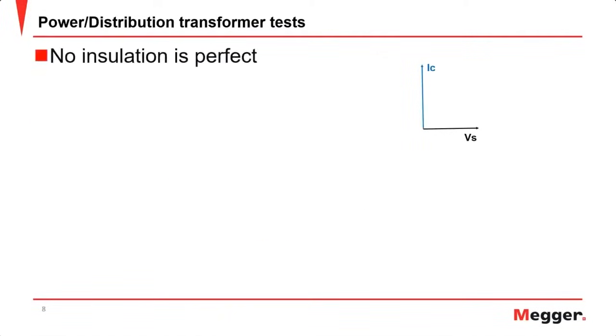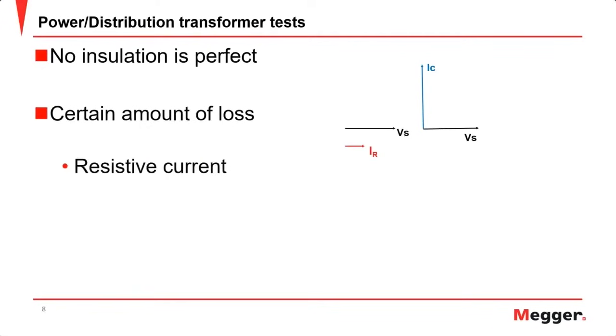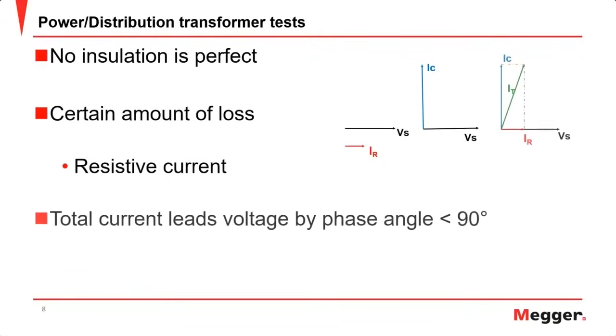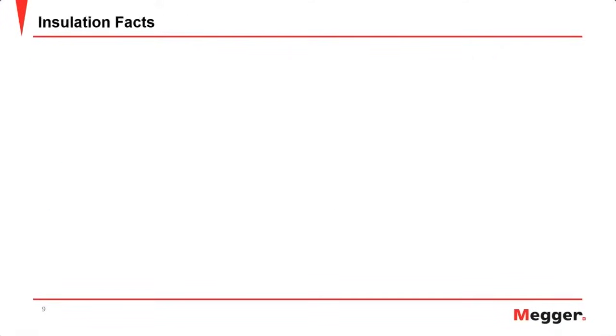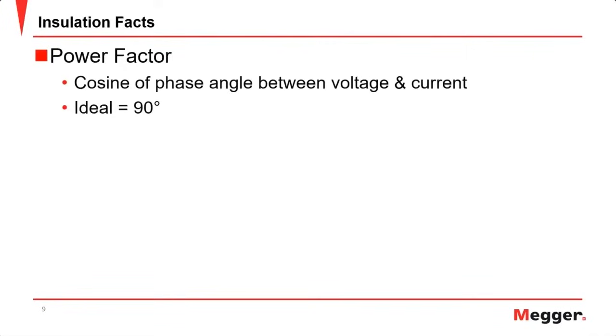But no insulation is perfect. And what you will see is that there is a certain amount of loss that shows up as resistive current. So then this total current will lead the voltage by a phase angle that's less than 90 degrees. And this is how we determine what the power factor is. And power factor is a calculation. It's the cosine of the phase angle between voltage and current. Ideally, that would be 90 degrees, as explained before.